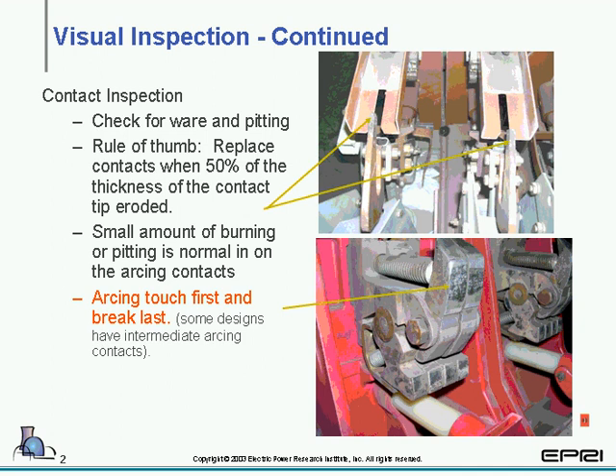Next item is a small amount of pitting is normal, and that can be shown in the bottom slide of the arcing contacts, but that is not true of the mains. The mains should be true and smooth and not appear to have taken any type of arcing load. And for those taking the test, you might want to pay attention to the last item. Arcing contacts touch first and break last.